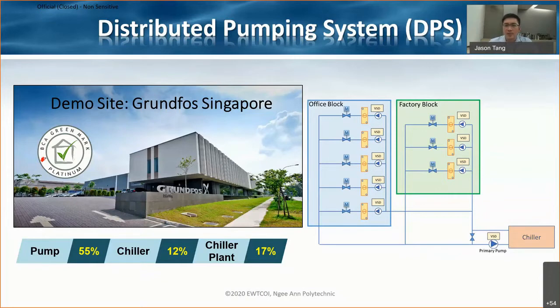Even though we downsized it three times, we now have distributed pumps at every level, hence the name distributed pumping system. We have decentralized pumps because we're no longer just pushing water, we're pushing as well as drawing water, so the head you need to overcome is a lot less.